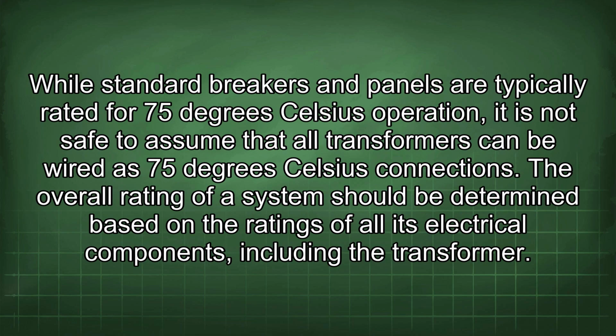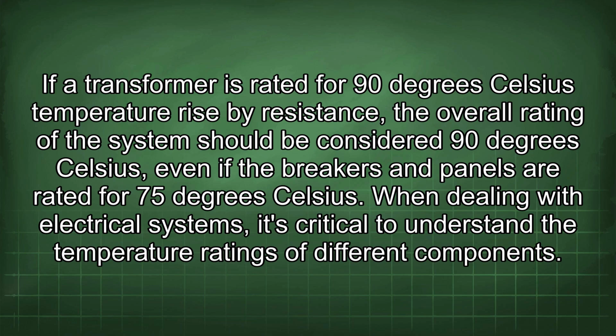While standard breakers and panels are typically rated for 75 degrees Celsius operation, it is not safe to assume that all transformers can be wired as 75 degrees Celsius connections. The overall rating of a system should be determined based on the ratings of all its electrical components, including the transformer. If a transformer is rated for 90 degrees Celsius temperature rise by resistance, the overall rating of the system should be considered 90 degrees Celsius, even if the breakers and panels are rated for 75 degrees Celsius.